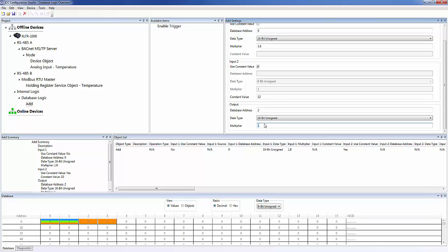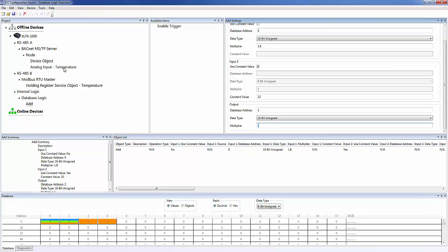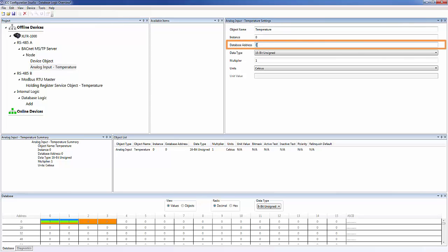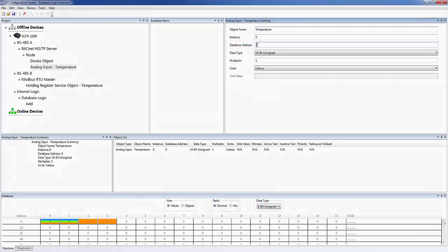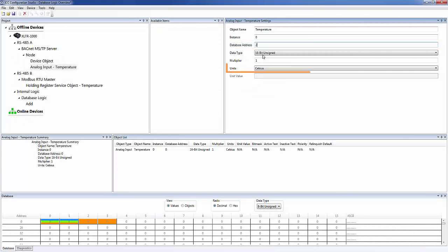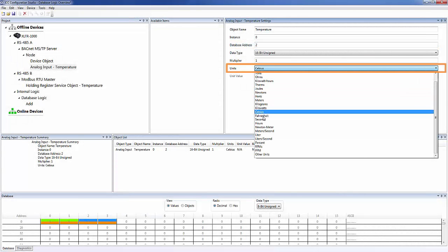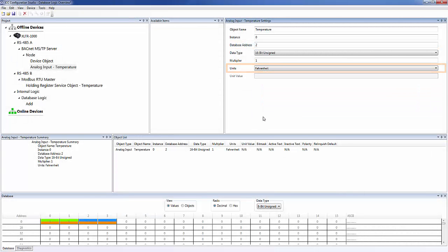The last thing we need to do is change our BACnet object mapping to use the new Fahrenheit temperature value. We need to change the database address to 2, to map it to the output of the add operation. We'll also go ahead and change the units to Fahrenheit. And we're done.